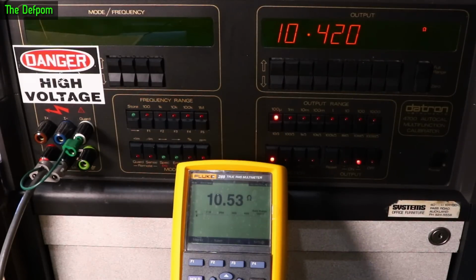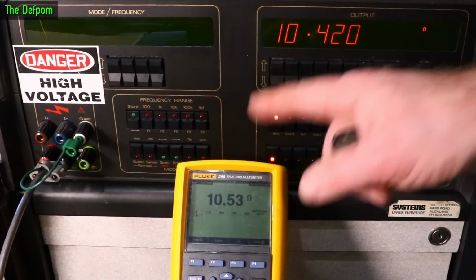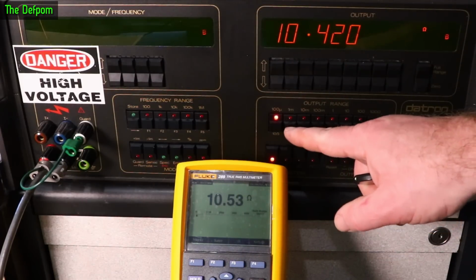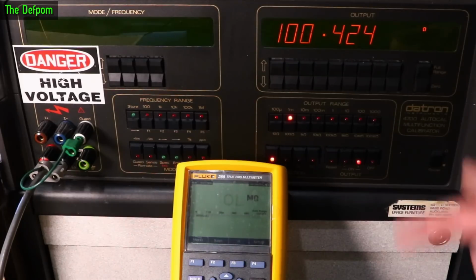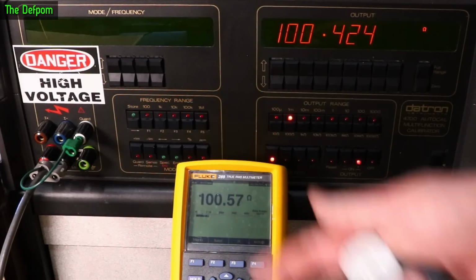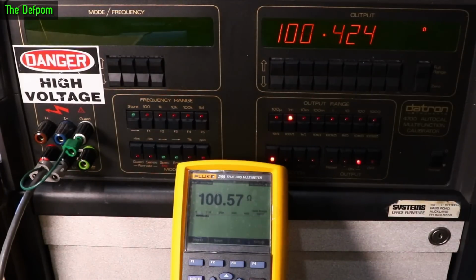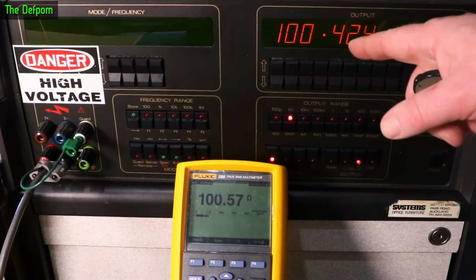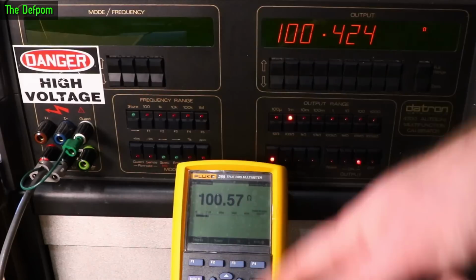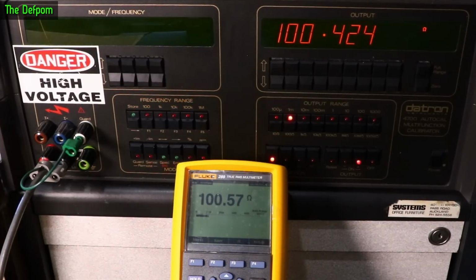I do actually have my Fluke calibrator up here. I might actually flick onto that as well afterwards. So 10 ohms is very close. Lead resistance and stuff like that are a bit of an issue when you've got things like this, which is just a 2-core lead. It's only doing 2 wire resistance, don't forget. That does affect the readings a lot. 100 ohms is basically right, so you have a very little difference there, again because of lead resistance and so on. Mind you, lead resistance was 0.1 ohms, wasn't it?